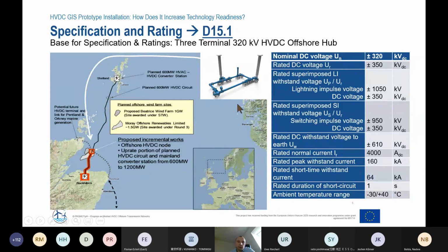There we had some specifications of what an HVDC GIS must be capable of to be used in this offshore hub. And as a manufacturer, we then came up with ratings that cover these specifications, and in some cases also slightly surpass them. But the GIS would be capable of handling these specifications. And the rating that was used was a 320 kV HVDC GIS with a rated voltage of 350 kV DC. We have a lightning impulse level of 1050 and a switching impulse level of 950. All of this, of course, also superimposed with the rated DC voltage. We have a rated DC withstand voltage to earth of 610 kV and 4000 amps rated current. And it can be operated in an ambient temperature range of -30 to +40.